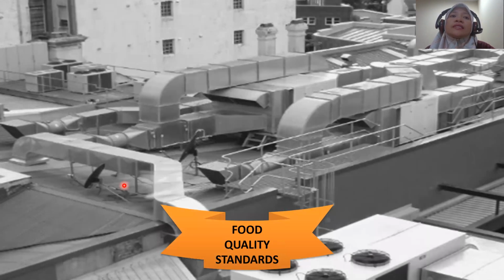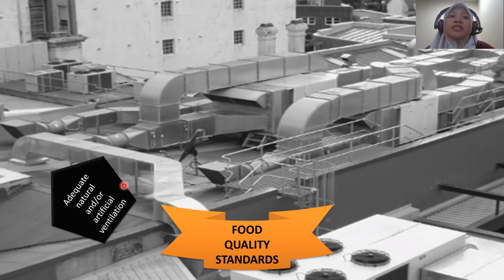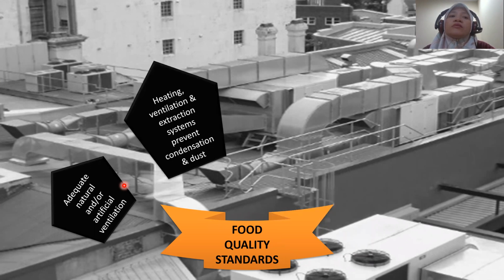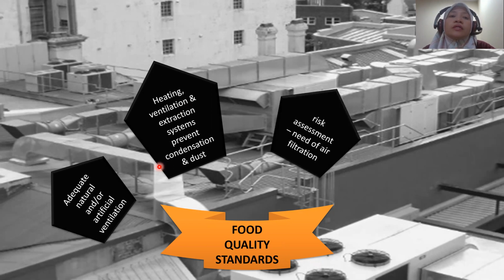Food quality standards provide some guidance on ventilation and air filtration, which typically state that adequate natural or artificial ventilation shall be provided. It also states that heating, ventilation, and extraction systems must be effective at preventing condensation and excessive dust. It also requires that a documented risk assessment must be conducted to determine the requirement for air filtration.